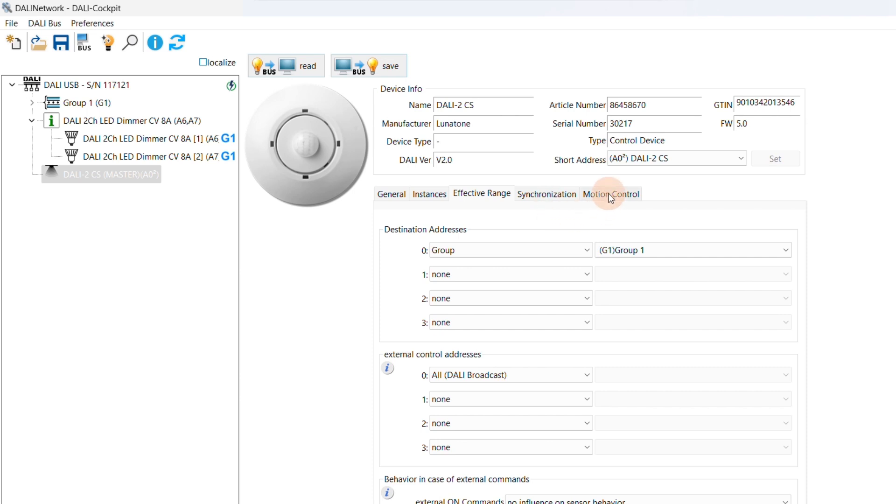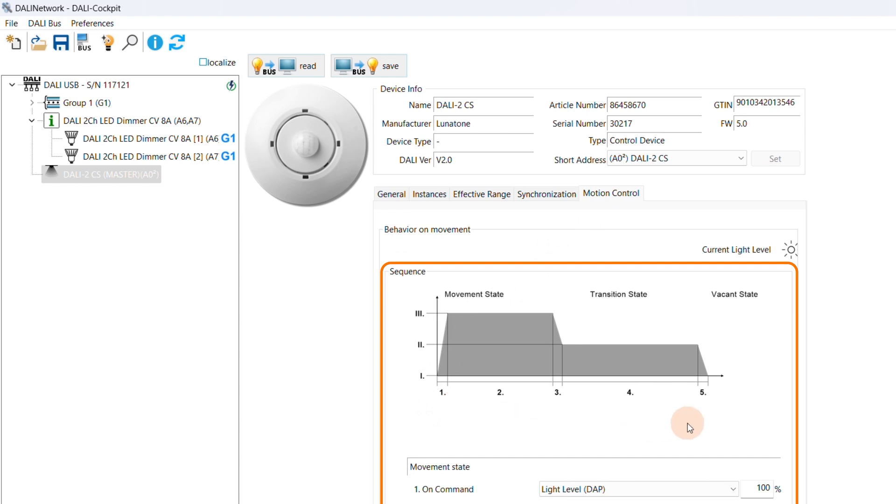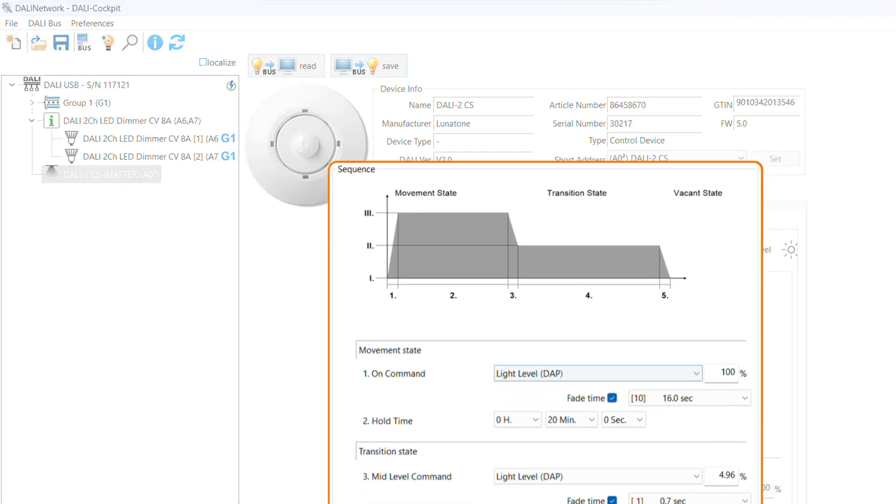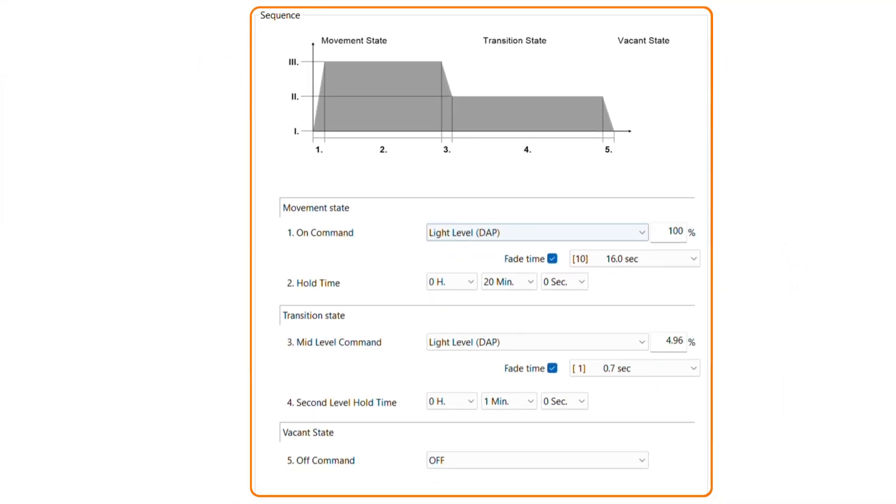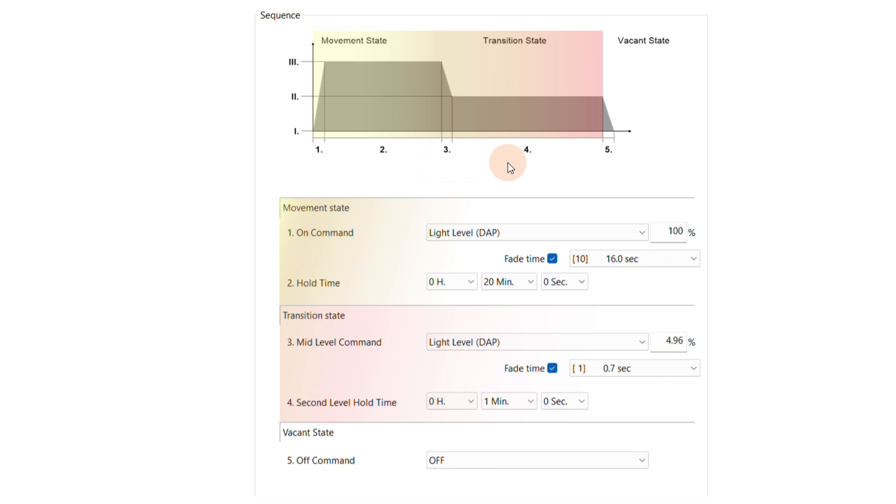Let's open the tab Motion Control. Here we can define how luminaires should react when motion is detected. The graph in the center shows three states. First is the movement state, which defines what happens when movement is detected. Next is the transition state, where the light typically fades to a different level. And lastly, the vacant state, which completes the sensor activity.